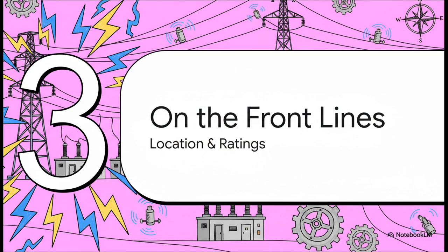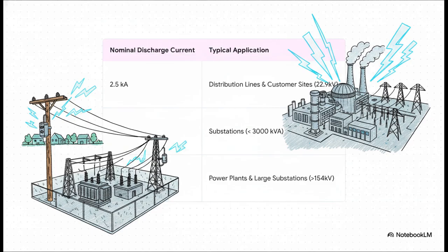All right, so that's all the theory, but how does this stuff actually get used out in the real world? Because where you put an arrestor and which one you pick, well, those are some seriously important decisions. Arrestors are rated by how much current they can handle, which is measured in kiloamperes, or kA. And it makes total sense, right? The rating gets bigger depending on how critical the location is. So a 2.5 kA arrestor is perfect for protecting the local power lines on your street. But for the massive power plants and major substations, yeah, you're going to need the big guns, the 10 kA units.